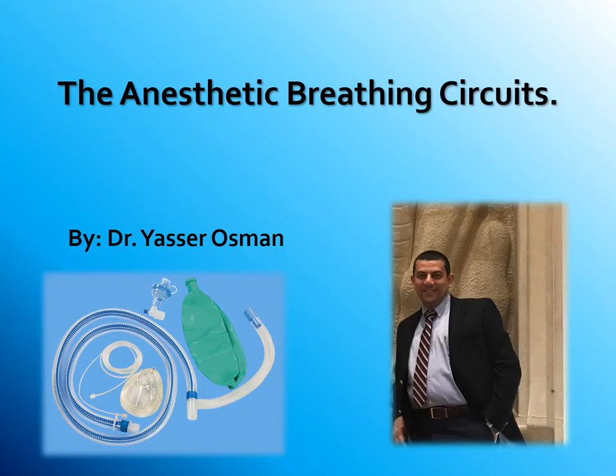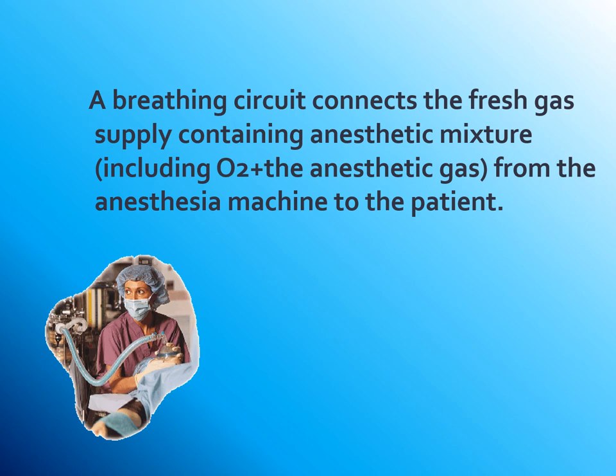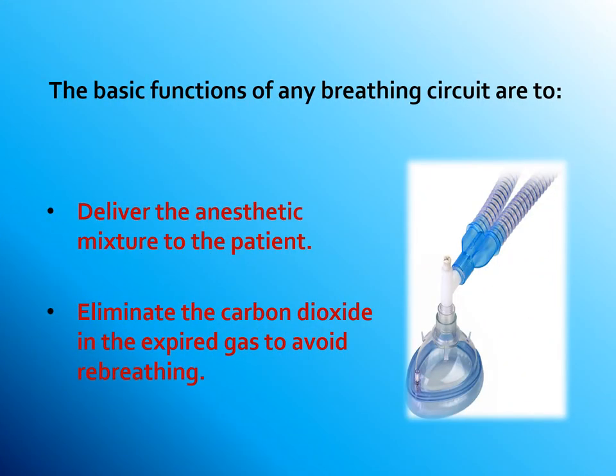Good day to you all. My name is Dr. Yasser Osman and I'm going to talk about the anesthetic breathing circuit. A breathing circuit connects the fresh gas supply containing the anesthetic mixture, namely oxygen and the anesthetic gas, from the anesthetic machine to the patient. The basic functions of any breathing circuit are to deliver the anesthetic mixture to the patient and eliminate carbon dioxide in the expired gas to avoid re-breathing.